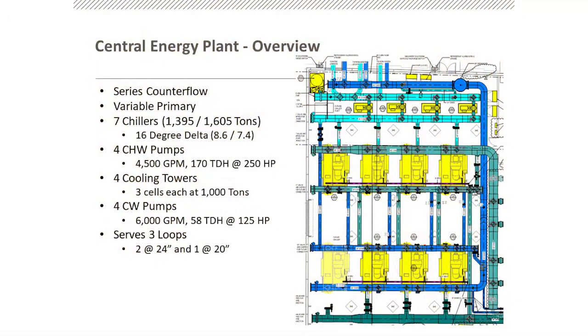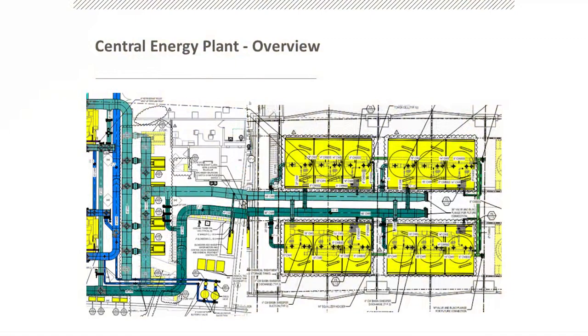So, chiller plant, it's pretty big. As you see on the screen, that's the image on the right-hand side. It is a series counterflow chiller plant. It is variable primary. You can see the different chillers there. There are 7. They're not equally sized, right? Because they're considered upstream and downstream chillers, very typical that you see in a series counterflow. But I said there are 7. We'll get into that a little bit later on. 4 chilled water pumps. You only need 3. 4 cooling towers with 3 cells each, but technically per the load, you only need 3.